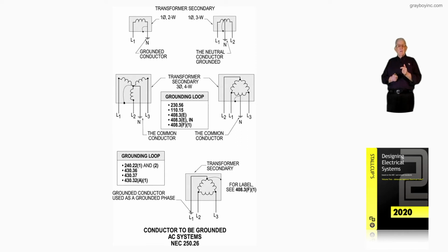You've got to bring that grounded conductor in for an effective ground fault path, like on 277-480, even though you only had three-phase equipment and you set a main and fed a separately derived system and stepped the voltage down to 120-208, basically. That's what we're talking about.